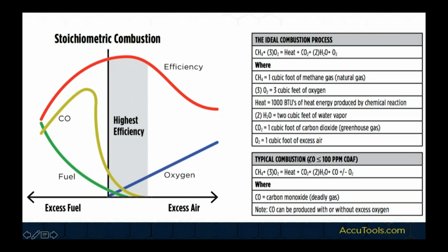And when we look at typical combustion, we end up with some CO in there. Now, if you have enough excess air and the burner's burning well, you likely will get no CO in the flue gases, but many, many burners produce a small amount of CO in the flue gases. No matter what you do, sometimes you have to resign yourself to the fact that there's going to be a small amount of CO produced.